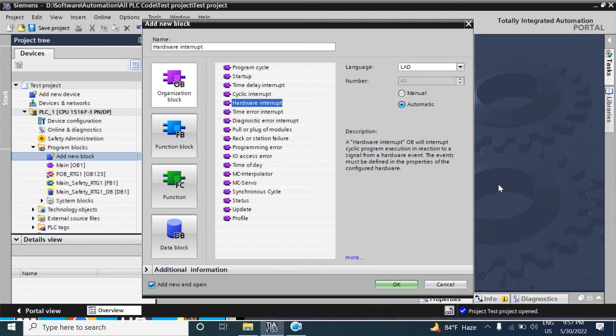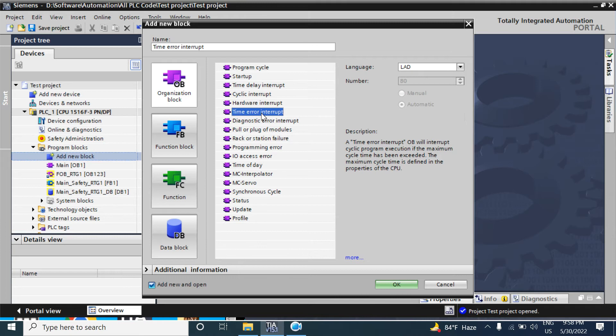The next one is Hardware Interrupt. This OB block is not for all modules — it is only for dedicated high-feature modules, like digital high-feature modules or analog high-feature modules. Those high-feature modules have the hardware interrupt function, so you can use this OB only when you have a high-feature module in your project; otherwise it will not work.